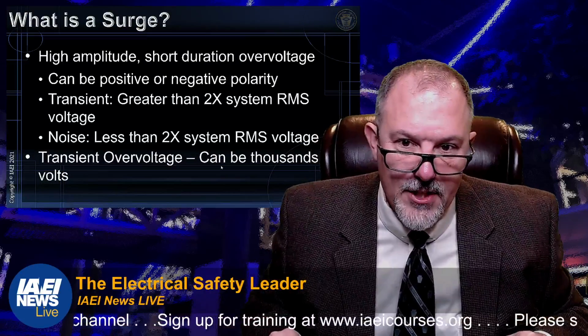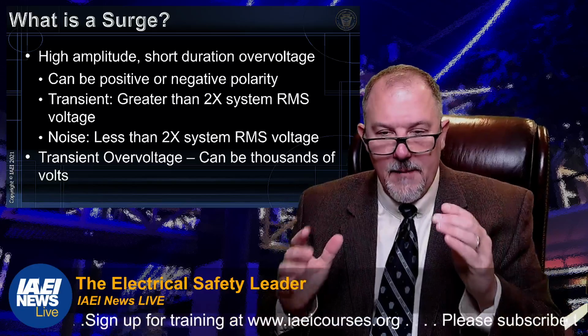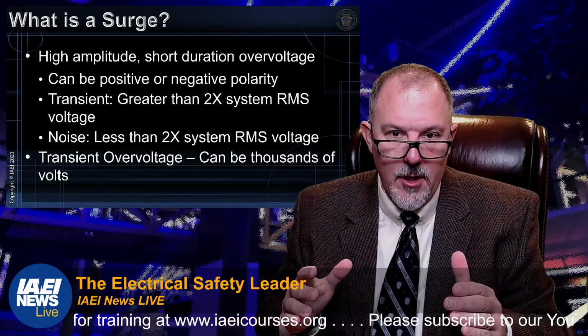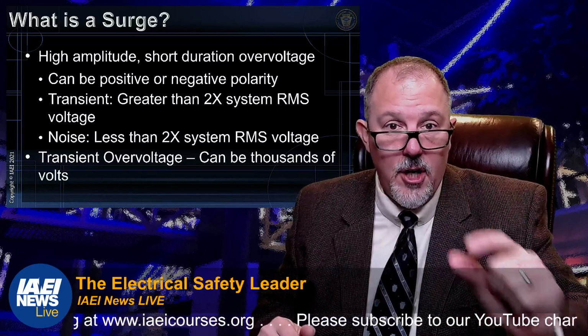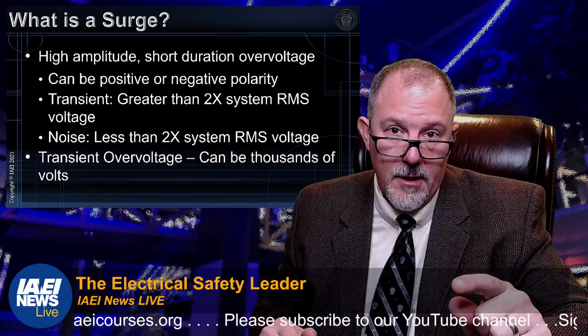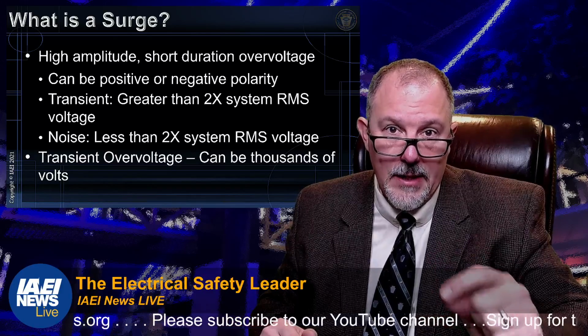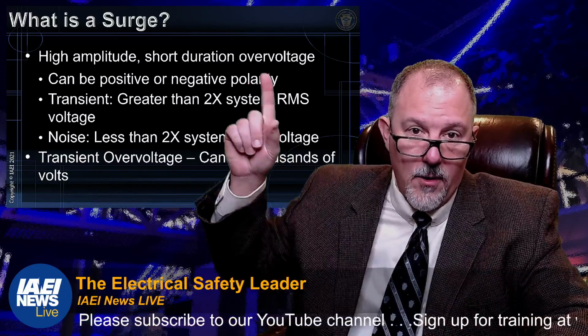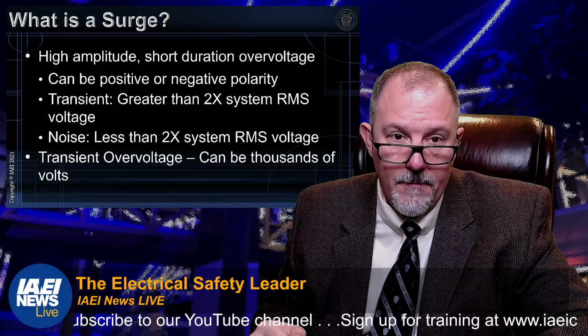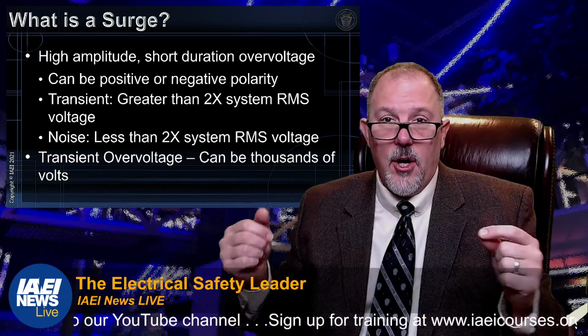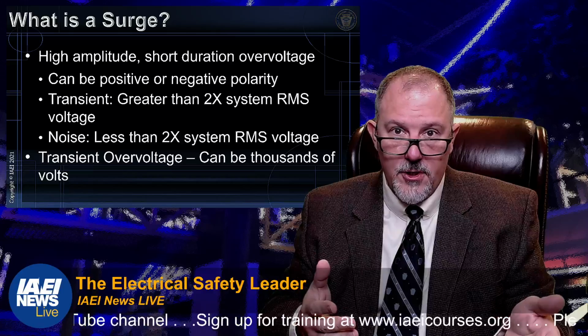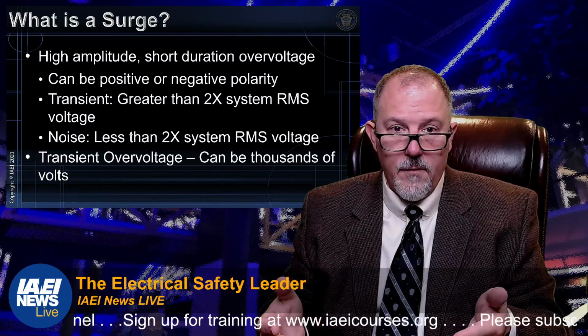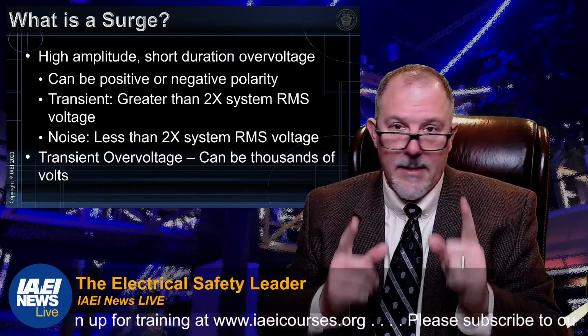So what is a surge? We're talking about high amplitude but short duration overvoltages. Now, this is where some people get a little confused because of that word overvoltage. They'll say all overvoltages are surges and all surges are overvoltages. We're going to get to that. That's not true.